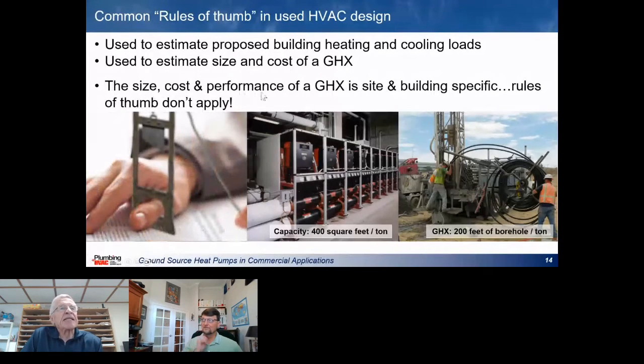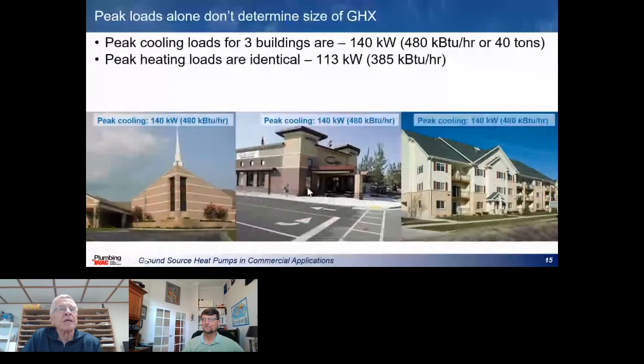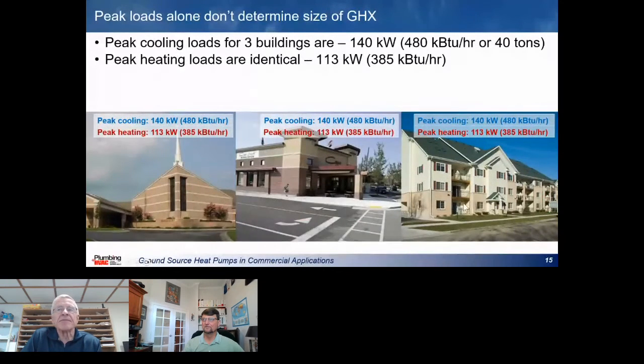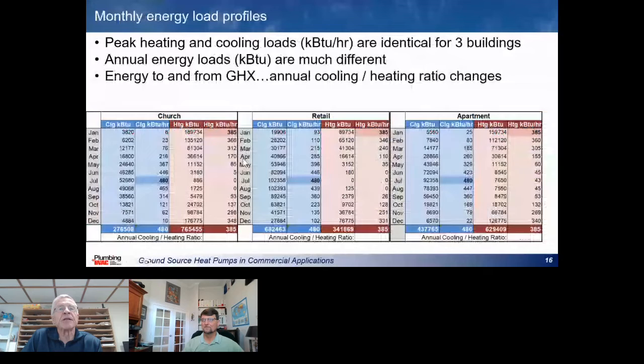The problem is that the size and the cost and the performance of a ground heat exchanger is very site and building specific. Rules of thumb don't really apply to these systems. As an example, if we were looking at 3 buildings, a church, a retail store, and an apartment building, they may all have exactly the same peak heating and cooling loads: 140 kilowatts or 480,000 BTUs per hour or 40 tons of cooling, and 113 kilowatts or 385,000 BTUs per hour in heating. These loads might be identical. And if you applied those rules of thumb, 40 tons times 200 feet per ton, the rules of thumb would suggest you need about 8,000 feet of drilling.